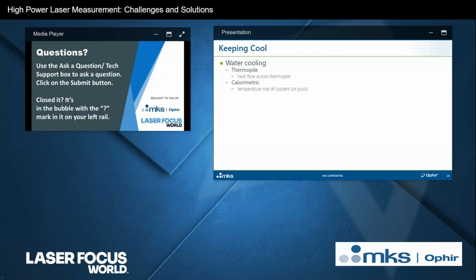One is the basic thermopile type that we already saw. Okay, they generally look like this, and you can see the water connectors there. That's an Ophir 5 kilowatt sensor, and the cooling water flows inside the body of the sensor, usually around channels that are built into the sides of the disc that's inside the sensor, the sensing element itself, and the cooling water obviously removes the heat from the sensor.